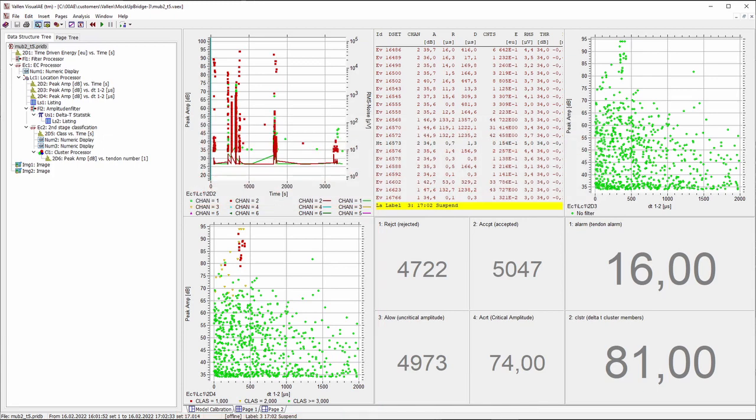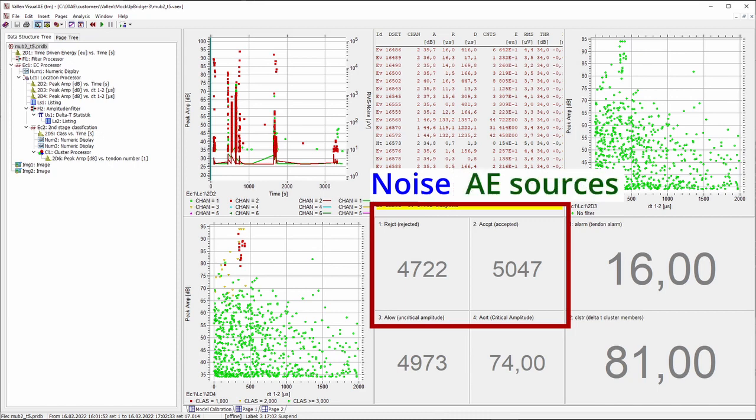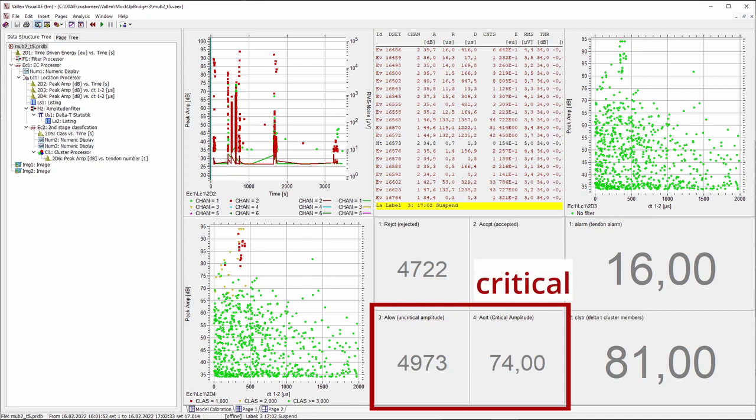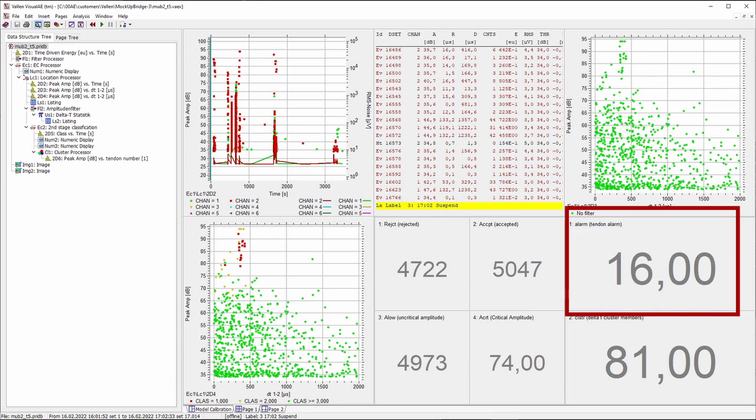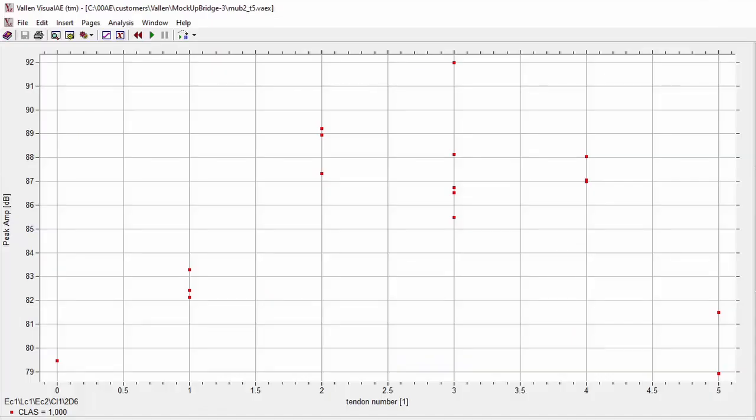In the first step, noise signals are discriminated from signals of distinctive sources. The analysis further categorizes signals into critical intensity and non-critical intensity as well as locatable and non-locatable signals. All of the information is combined to a result that is either a possible failure mechanism such as a wire failure or unwanted signals coming from spurious noise sources. Finally, the analysis tries to assign the signals to a specific tendon.